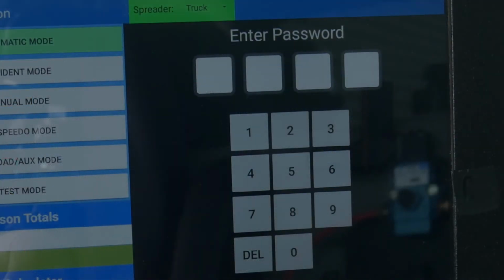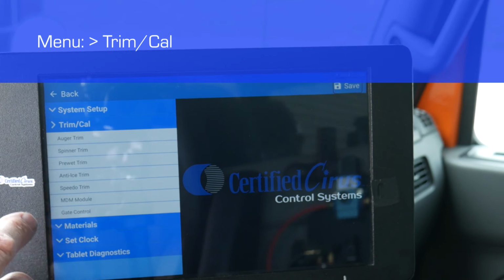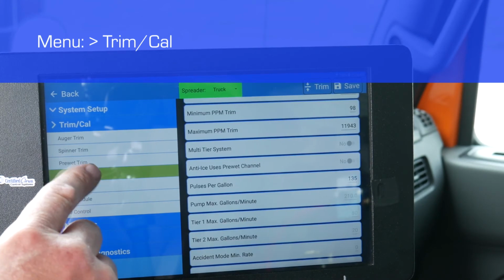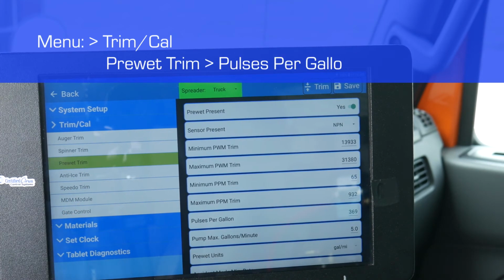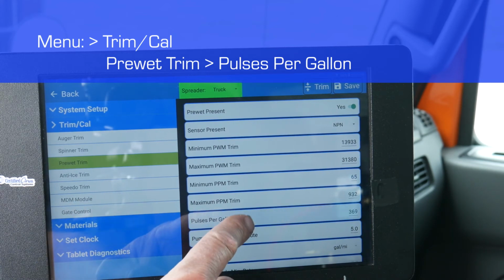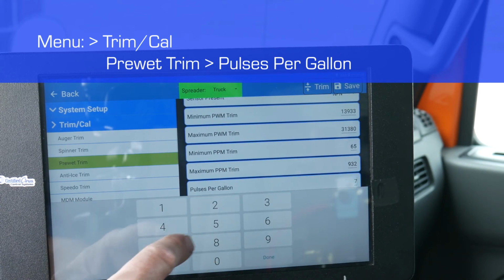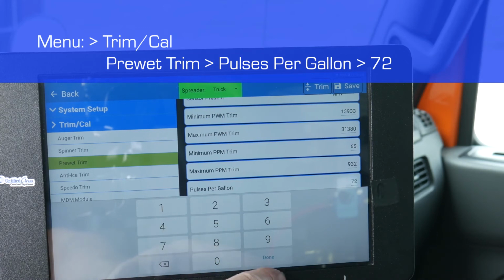Enter the configuration screen from the main menu. The screen will prompt you for the password. Select Trim Cal from the menu, then select Pre-Wet. Scroll to Pulses per gallon, then enter the value you calculated from the flow meter, in this example, 72.